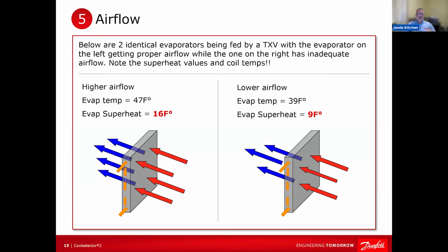Okay? Yeah, you can tear that compressor apart and Copeland or Bitzer or somebody will tell you it overheated, it flooded, right? Whatever. But there's a lot of different things that can cause those same problems, right? You can have an oil issue due to temperature, due to low oil, due to no oil return, due to liquid return. All these things can cause lubrication failure. So you need to be able to go through and be a detective, put your detective hat on and look at the clues.